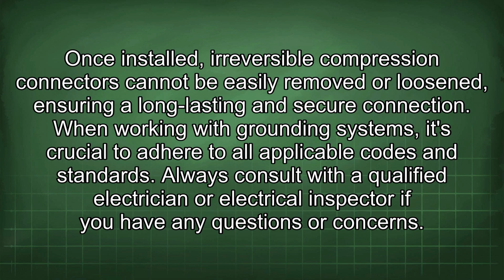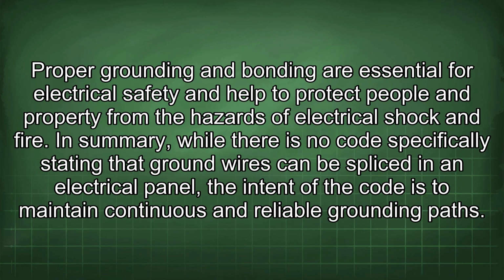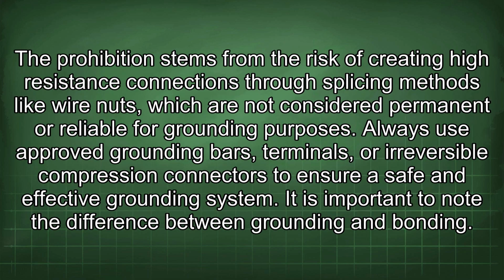When working with grounding systems, it's crucial to adhere to all applicable codes and standards. Always consult with a qualified electrician or electrical inspector if you have any questions or concerns. Proper grounding and bonding are essential for electrical safety and help to protect people and property from the hazards of electrical shock and fire. In summary, while there is no code specifically stating that ground wires can be spliced in an electrical panel, the intent of the code is to maintain continuous and reliable grounding paths. The prohibition stems from the risk of creating high resistance connections through splicing methods like wire nuts, which are not considered permanent or reliable for grounding purposes. Always use approved grounding bars, terminals, or irreversible compression connectors to ensure a safe and effective grounding system.